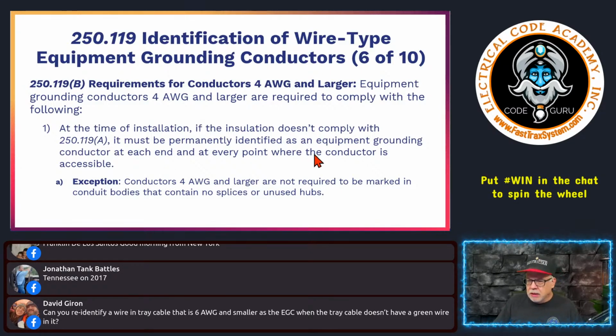Now, here's what it says, exception to this rule. Conductors 4 and larger are not required to be marked in conduit bodies that contain no splices or unused hubs. So if it passes through a conduit, through an LB, an LR, an LL, whatnot, and there's no splices in there, then what's the point of marking it? It just passes right through, so then you wouldn't have to do that, okay?